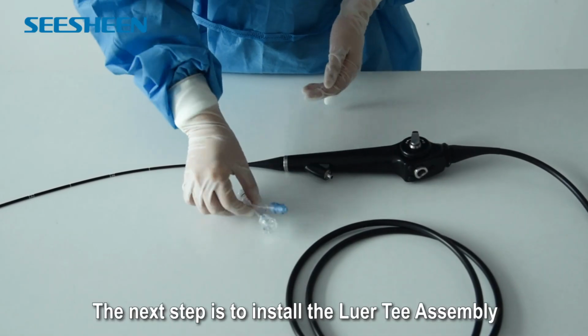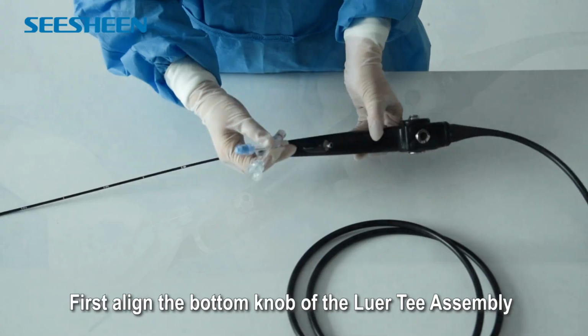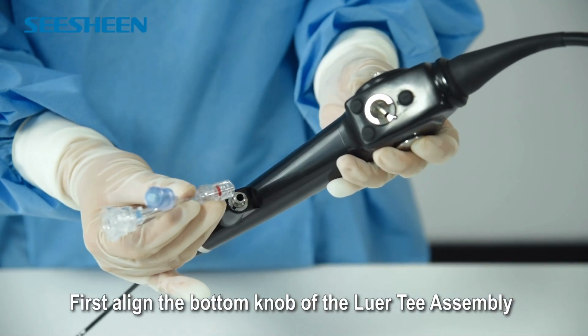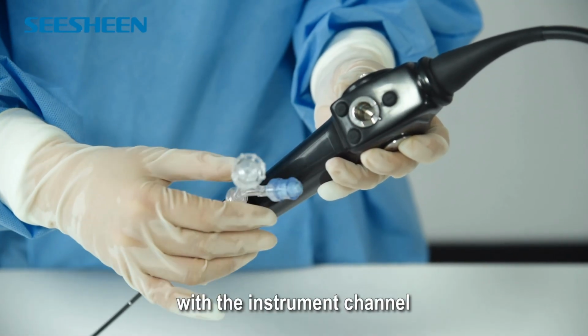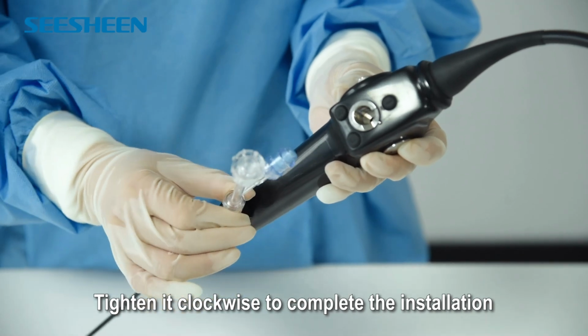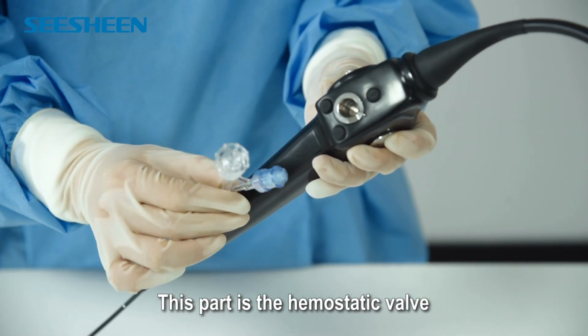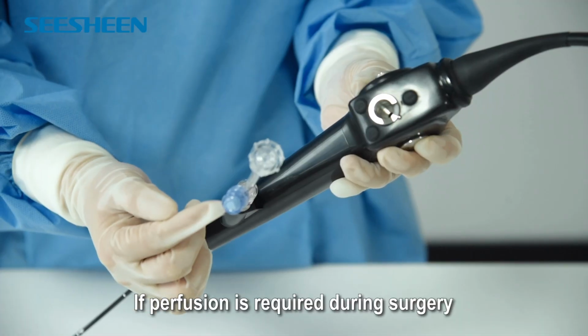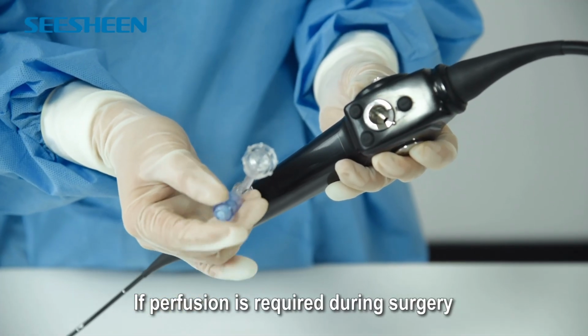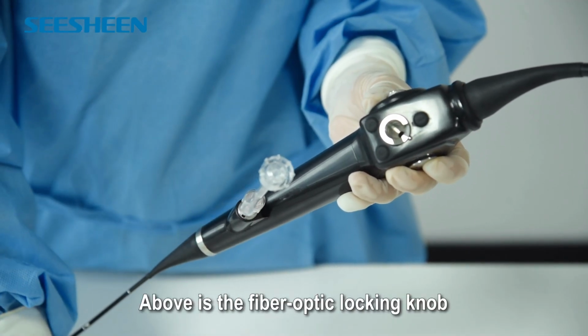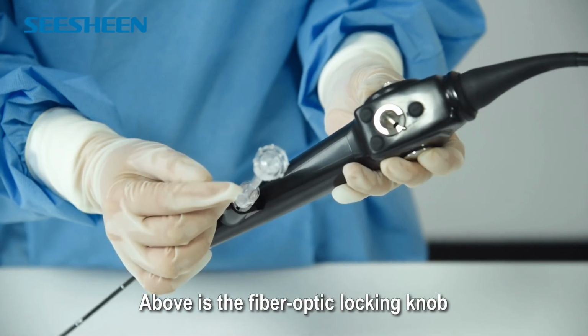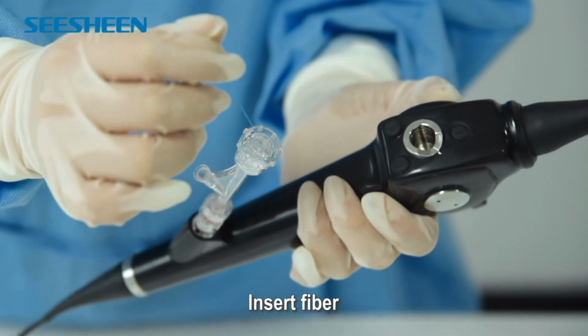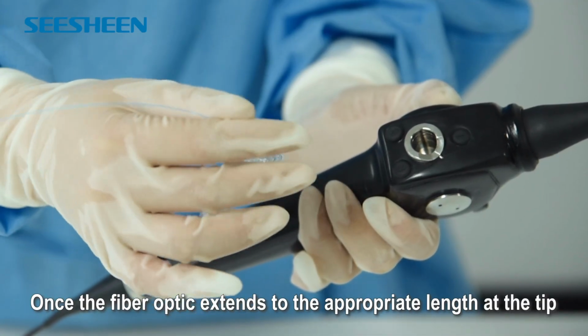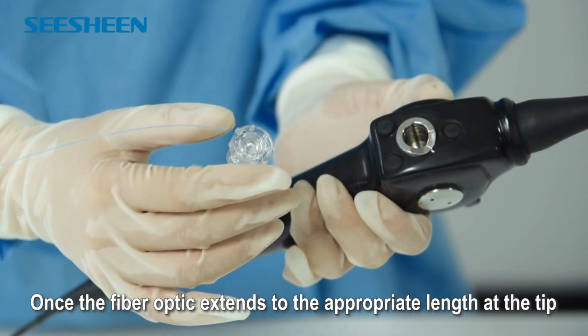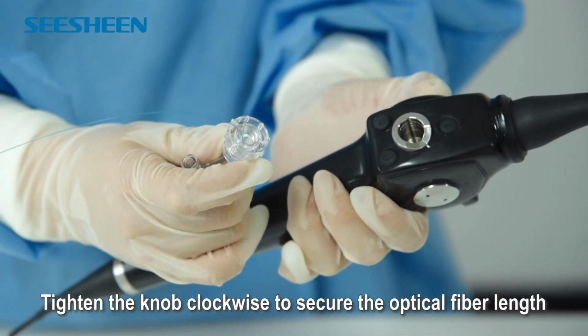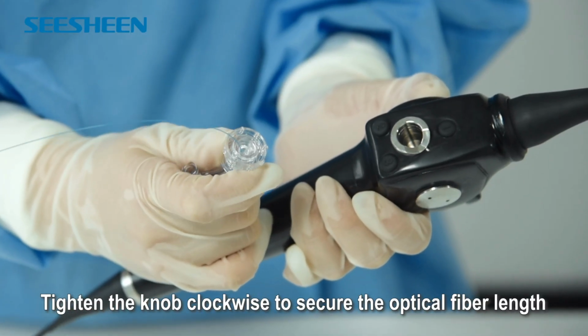Luer Tee assembly installation. The next step is to install the Luer Tee assembly. First, align the bottom knob of the Luer Tee assembly with the instrument channel. Tighten it clockwise to complete the installation. This part is the hemostatic valve. If perfusion is required during surgery, loosen it and remove it. Above is the fiber optic locking knob. Insert fiber. Once the fiber optic extends to the appropriate length at the tip, tighten the knob clockwise to secure the optical fiber length.